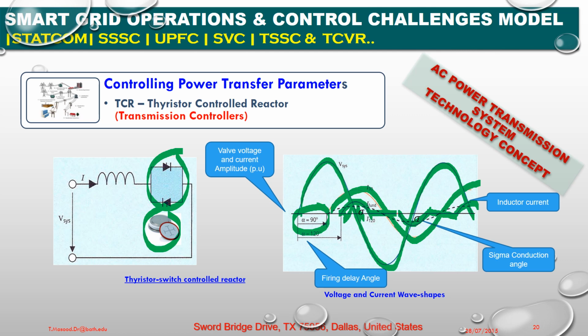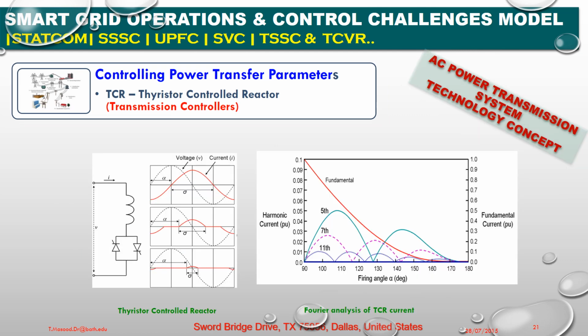In my next slide, this is TCR, thyristor controlled reactor. On the right hand side is my thyristor switch. In the first waveform, voltage versus current, when the firing angle or delay angle was 90 degrees, the voltage and current were in sinusoidal waveform. In the second case, when the firing angle changed from 90 to 120 degrees, the current waveform changed, and further, the conduction angle also changed.